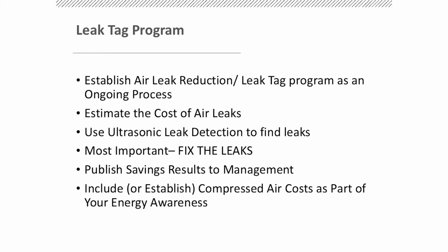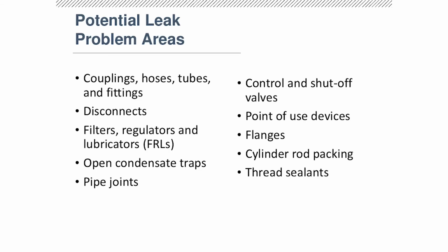I always talk about that because I had plants that did a great job of doing leak tags, putting it in their PM system. They just never went back and fixed them because they weren't able to get the money for the overtime on weekends. So you want to establish the reduction program on an ongoing basis. You want to use the detection to find the leaks. You want, most importantly, to fix them. The big thing is to always give the savings and results to management. And then you want to make it part of any energy awareness you have.